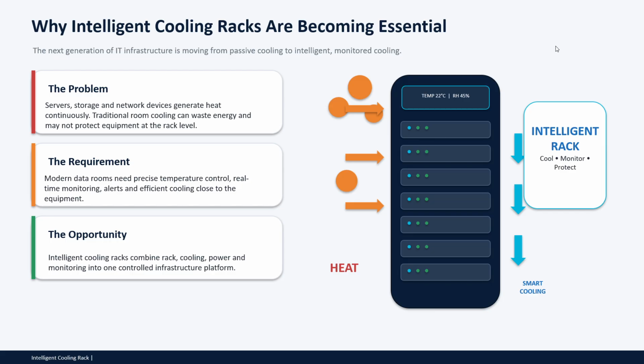This is when an intelligent cooling rack becomes important. An intelligent cooling rack combines the IT rack with advanced cooling, environment monitoring, intelligent power management and control systems. So instead of simply cooling the entire room, the system can provide more targeted cooling where it is actually required. The rack can monitor important parameters such as temperature, humidity, airflow, power consumption, rack condition and cooling performance.